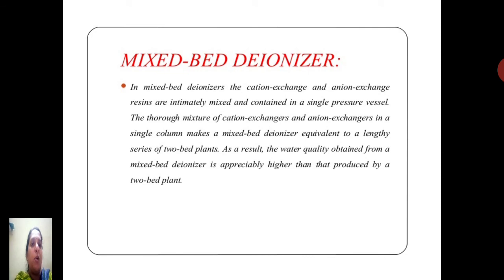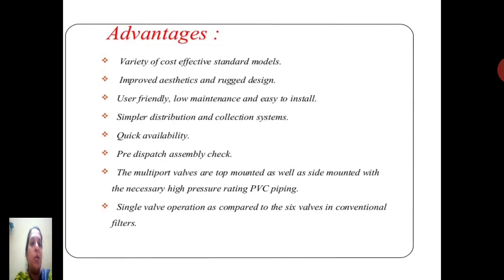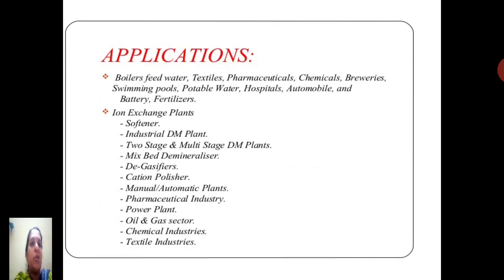As a result, the water quality obtained from a mixed bed deionizer is appreciably higher than that produced by a two bed plant. The advantages of this deionization are that a variety of cost effective standard models are available. It improves the aesthetics and design. It is user friendly, low maintenance and easy to install. It is simple in distribution and collection system. It has quick availability and pre-dispatch assembly is easy. The multi-port valves are top mounted as well as side mounted with the necessary high pressure rating PVC piping, and there is single valve operation as compared to the 6 valves in conventional filters.